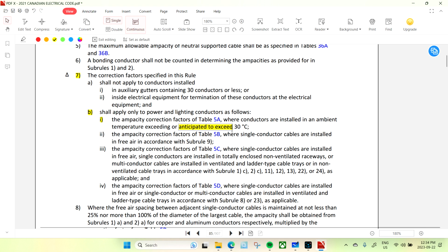Regardless, these are all 15 amp branch circuits for the solar panel system after the converter, and they were all done in number 12. The reason is because of the temperature that was expected to be seen in that attic. So all those NMD 90s were all run in number 12, not number 14, even though they were all 15 amp breakers or ampacity circuits.